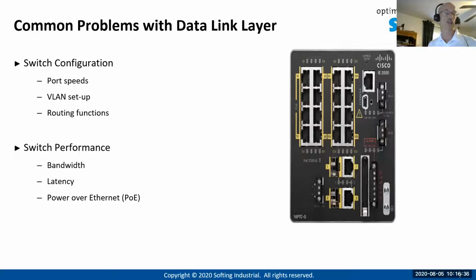A big trend too is powering devices on the plant floor from the switches themselves - that's a technology called Power over Ethernet, PoE. You already see it used to power access points and network cameras, and you may see more devices using that because it simplifies the wiring - you could just use the Ethernet cable to power something. But how do you know that switch is putting out enough power? How can you measure that? That's an issue, and there's usually a power budget issue as well with the switches.